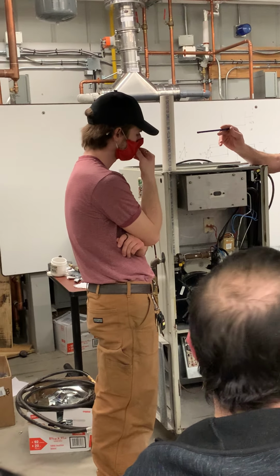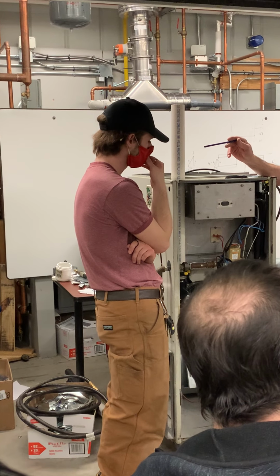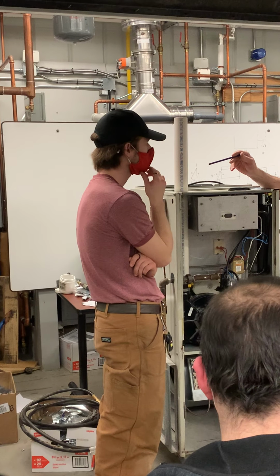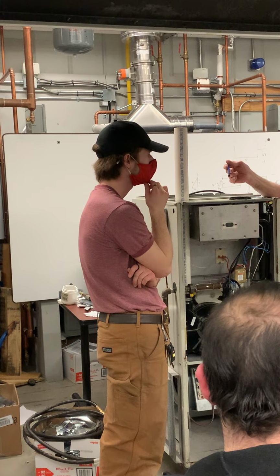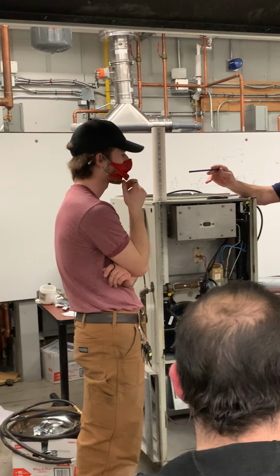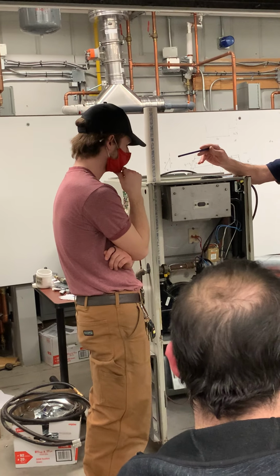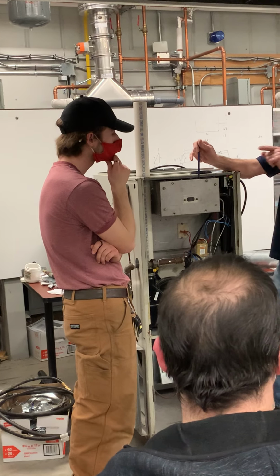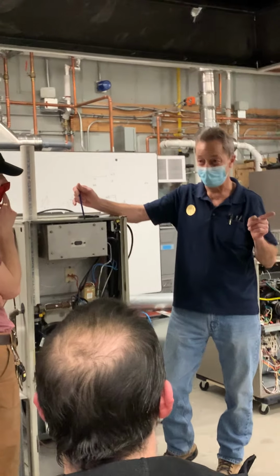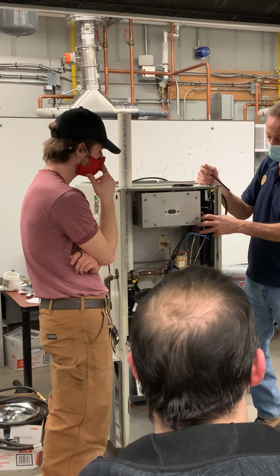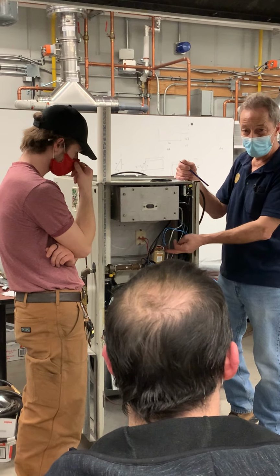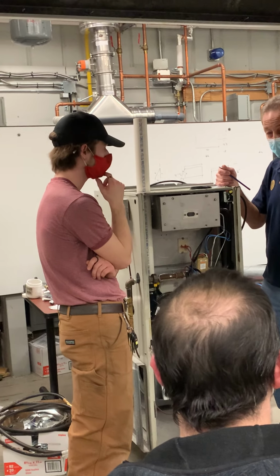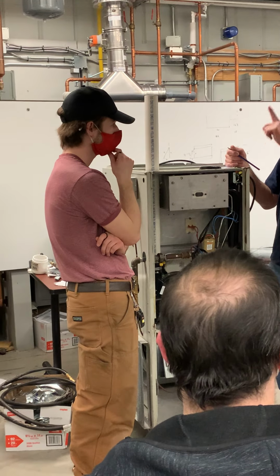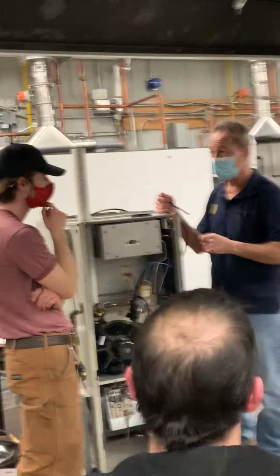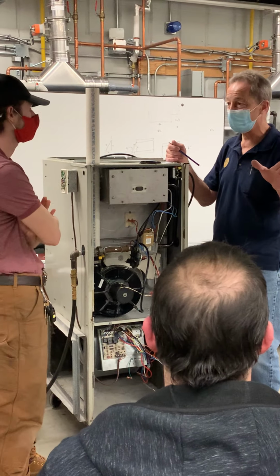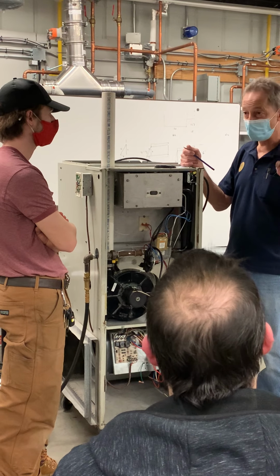Well, then it sent a signal to say that there was flame, and then it started. Not quite. On the Lennox G20, it's not quite as smart, is it? On the Lennox G20, as soon as the ignition controller energizes the pilot valve, remember that orange wire I told you about? It goes from the ignition controller, the orange wire energizes the pilot valve, and then it continues on to the board below. When that orange wire gets the signal, it says, okay, somebody upstairs is trying to get the main burner going, I'm just going to start timing. So it times for 45 seconds, then it starts the main blower. So that orange wire starts the main blower.